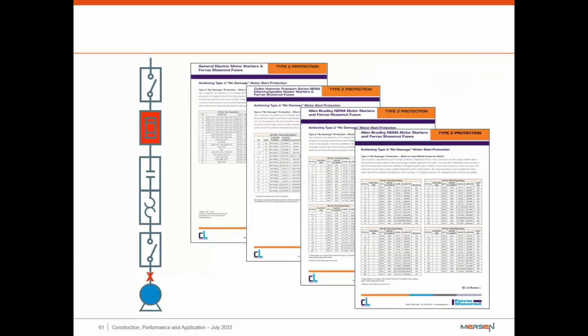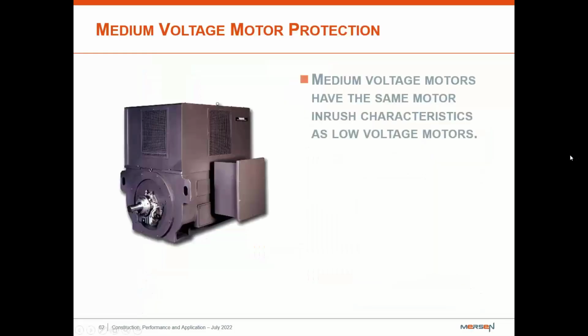So again, the manufacturers usually are going to tell you inside of their literature what style of fuse they believe that you should use or that they want you to use for the application, and you should always go with what they say because they've done testing to verify that. At Mersen, we usually collect the data on this different stuff ourselves. We will offer you the information for whatever the application is. We will help you find what the fuse is and size it correctly so that you're not damaging any equipment and that you do get the information. This is also all available online on our website, but upon request, we can get it to you as well.